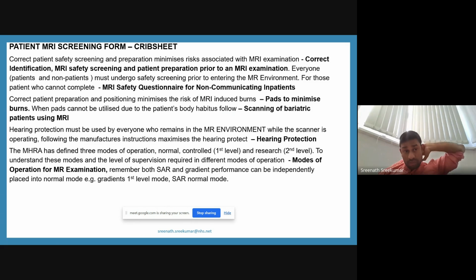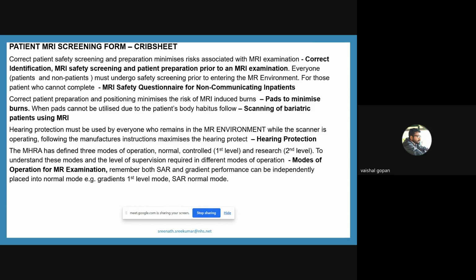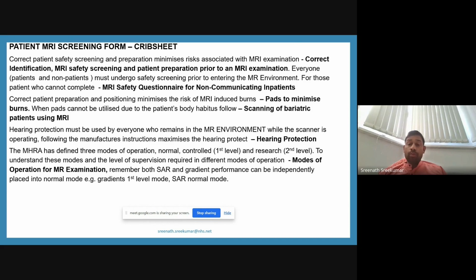Another one is hearing protection. You have to give hearing protection because MHRA has really influenced that: above 85 decibels, hearing protection should be given. So use hearing protection as much as possible: earmuffs for pediatric patients, or earplugs, and also soundproofing such as headphones, which some centers provide. MHRA has also defined modes of operation inside the scanner: normal mode, first level mode, or research mode. So we have to use the different modes of operation that are best for the clinical condition and the implant specifications.